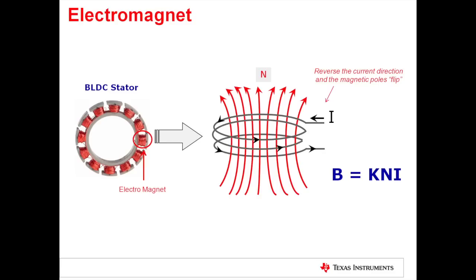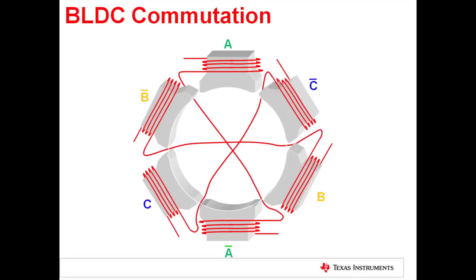Now let's take a look at how these electromagnets are used to spin a motor. So here we've got the stator again. We've got six poles this time, basically three pole pairs. And one of the first things to point out is how it's wound. The way they wound these motors is they use a single winding to create a pole pair. So for example A and A bar are actually the same winding. Each one of those A and A bar will create an opposite polarity, so a north and a south pole.